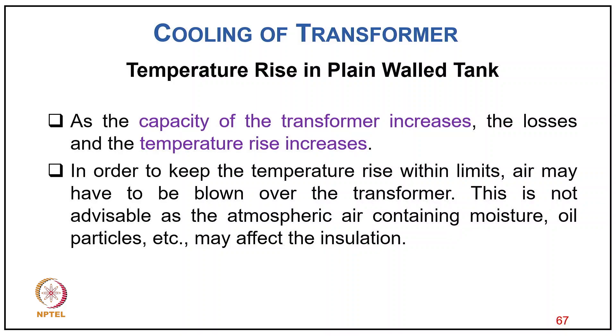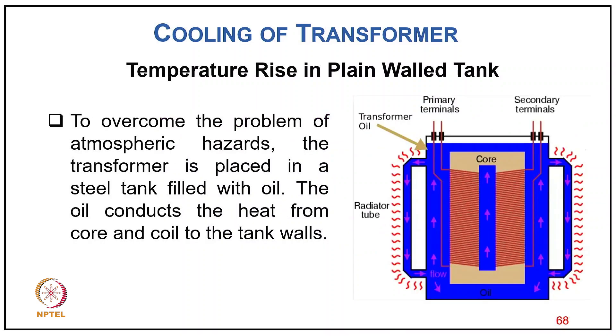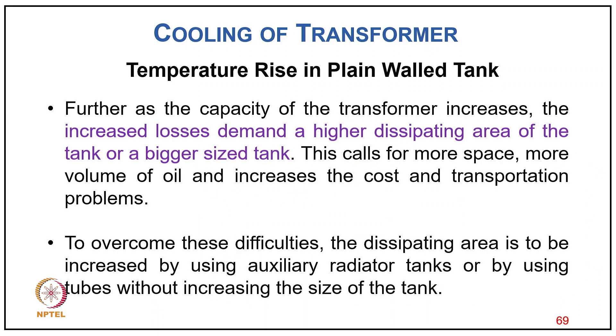As transformer capacity increases, losses and temperature rise also increase. To keep temperature rise within limits, air may be blown, but atmospheric air containing moisture and oil particles may affect insulation. To overcome this, the transformer is placed in a steel tank filled with oil, which conducts heat from core and coil to the tank wall. For larger ratings, the dissipating area is increased using tubes or radiators without increasing tank size.